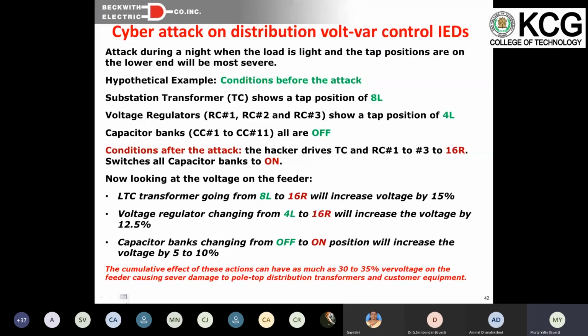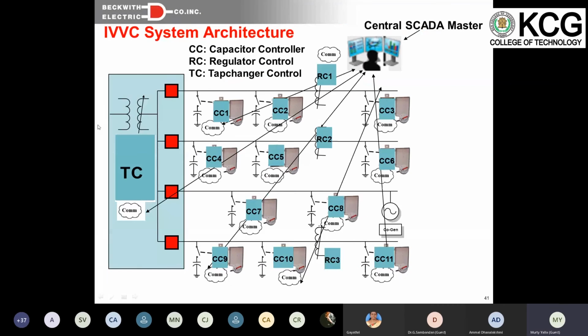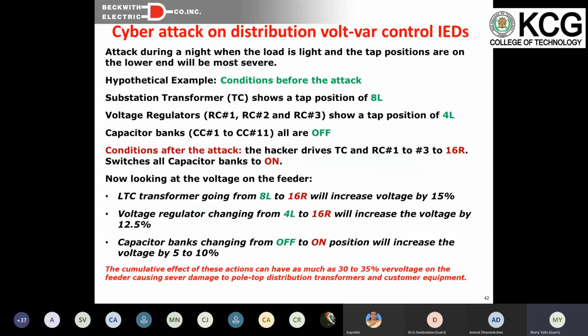So let's simulate an attack. Take this tap changer, let's say during the nighttime. It's actually worse than daytime, because at nighttime the load is light and your tap changers are on the negative end. That means maybe 8 lower. If it is 16 lower, you're at minus 10%. 16 raise, you're at plus 10%. From 8 lower to 16 raise, you increase the voltage by 15%.